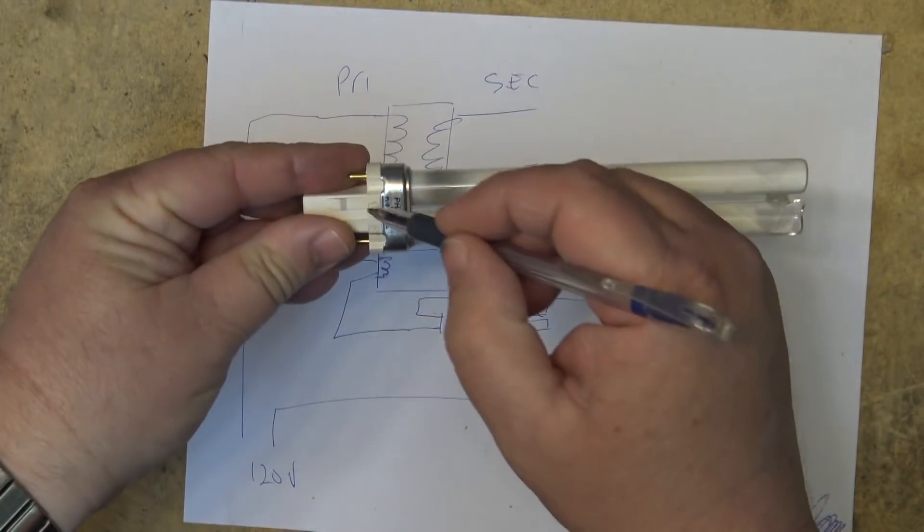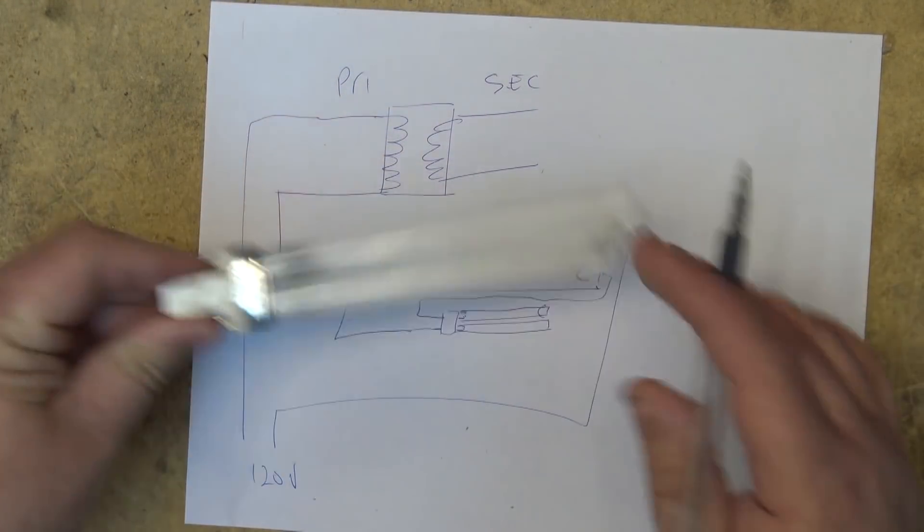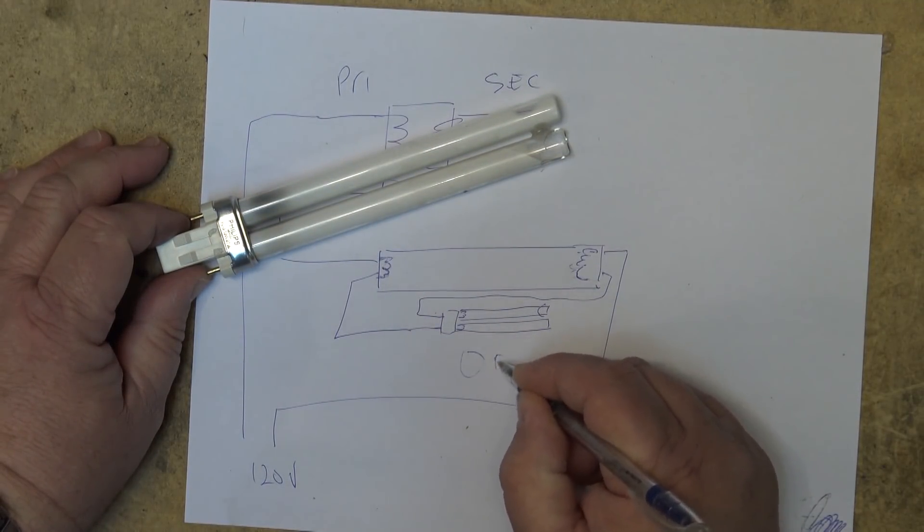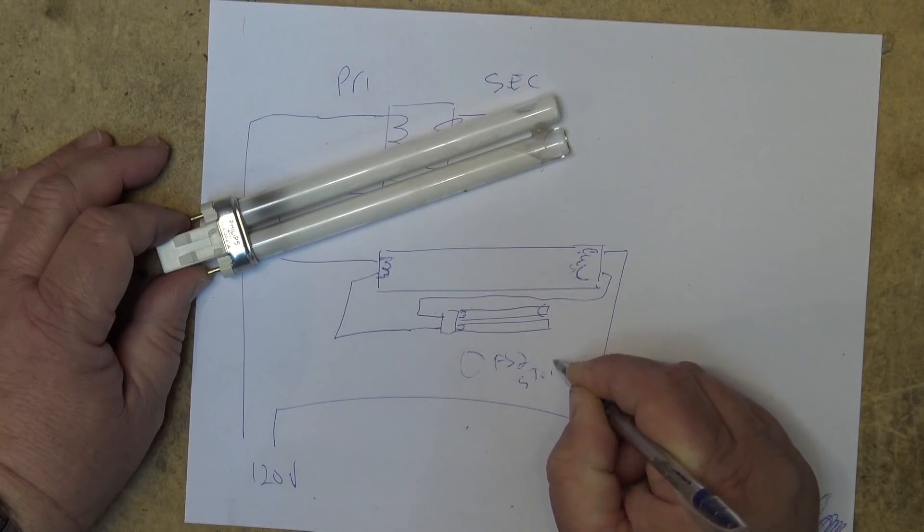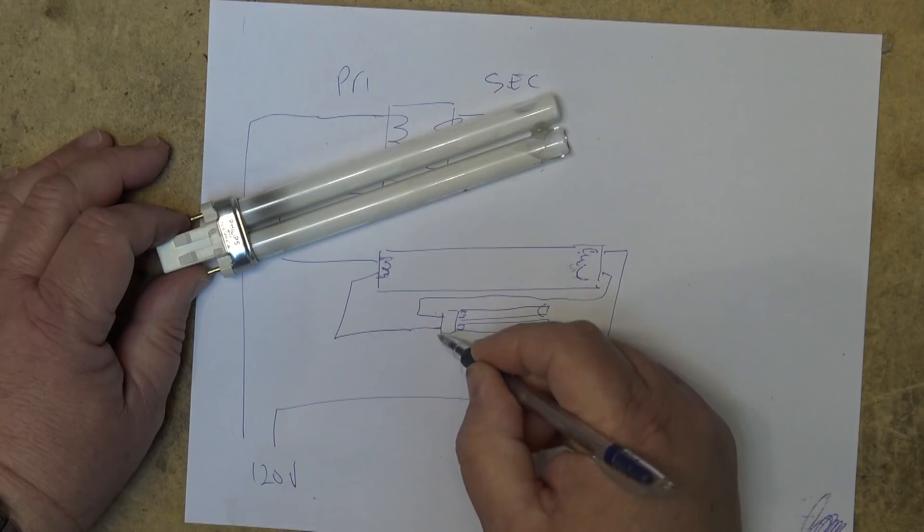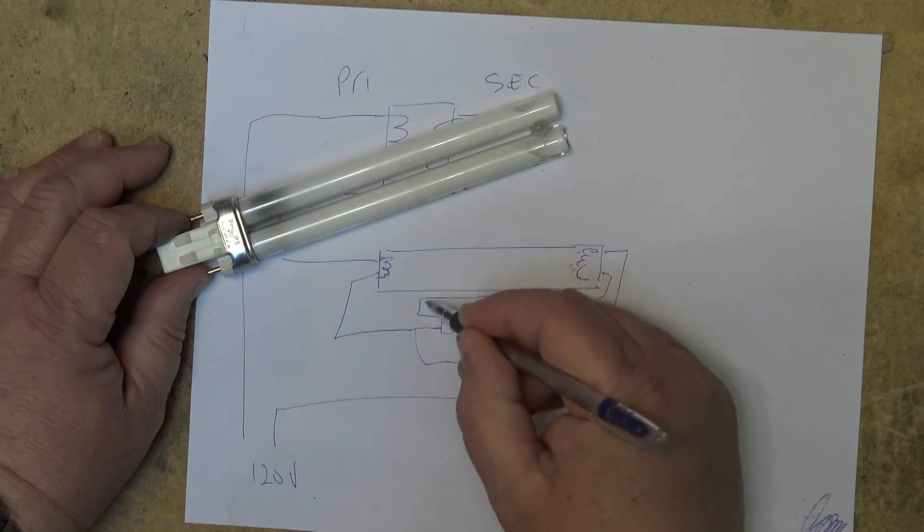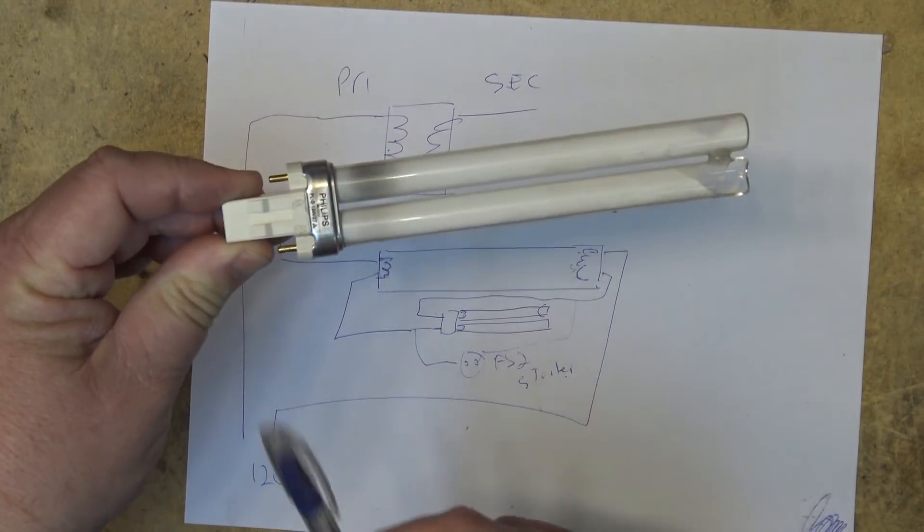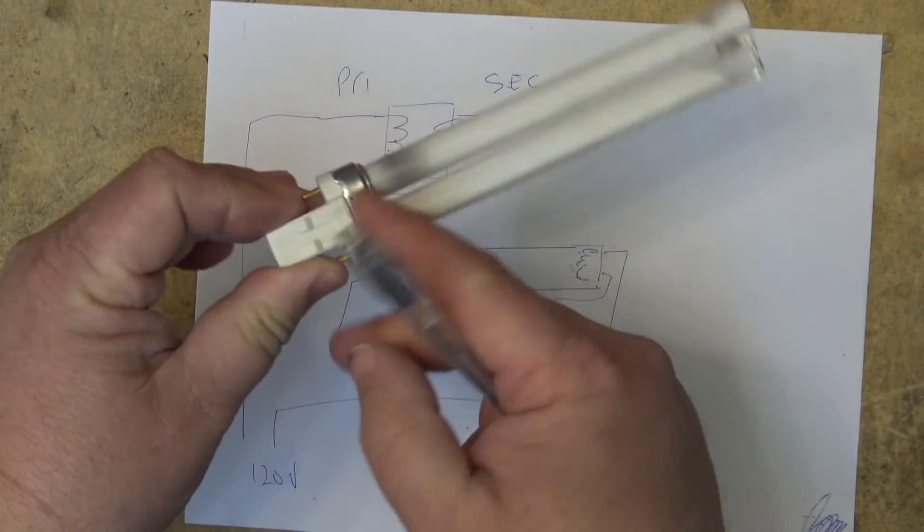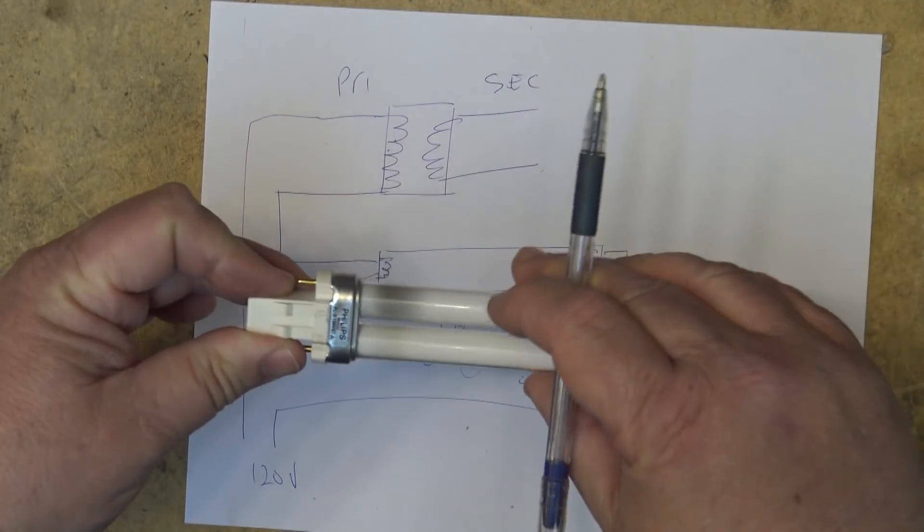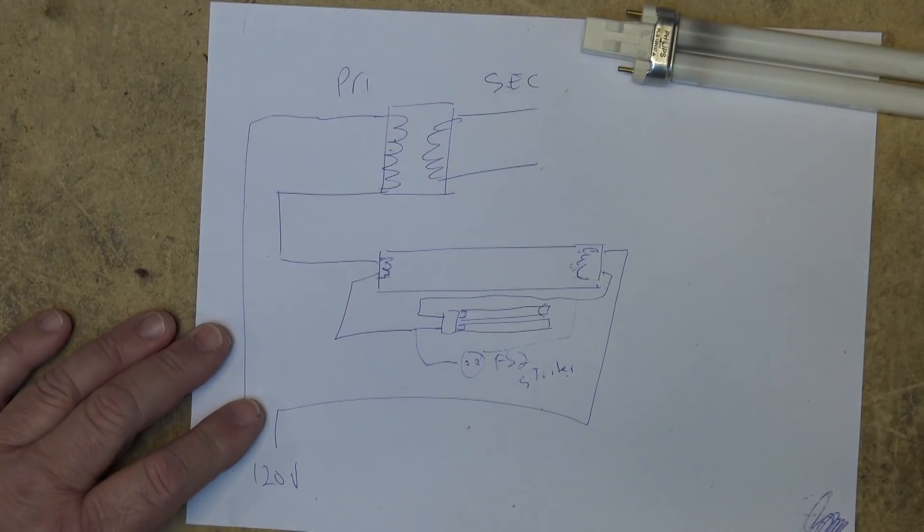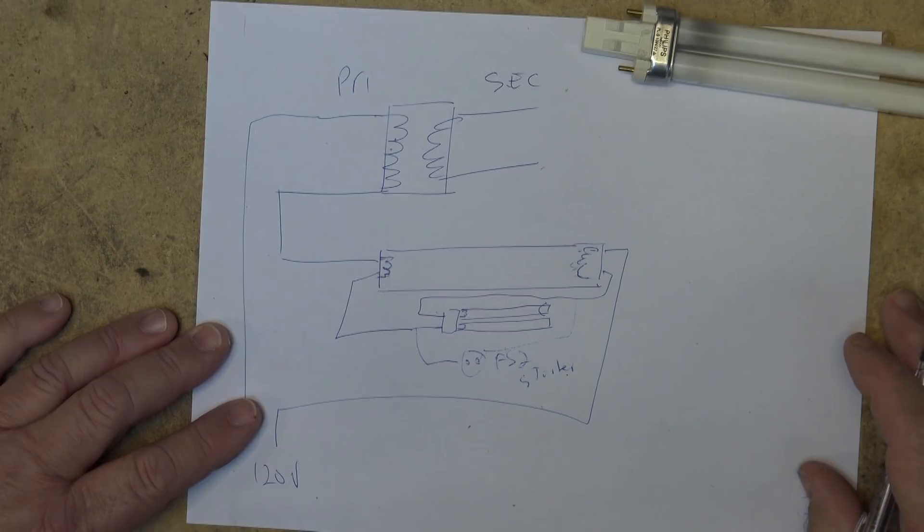So we need to limit the amount of current and we're going to use just the primary side because the fine wire that's wrapped around that primary side will give us a current lowering effect. It will give us resistance. It also has a second benefit because to start a fluorescent lamp, we need a high initial kick to start it. So what's going to happen is the power is going to come through the primary of a transformer, go into the fluorescent lamp, come out, go into one end of one of the filaments on here. Now remember, in between, inside the base of this lamp, there's a starter bottle.